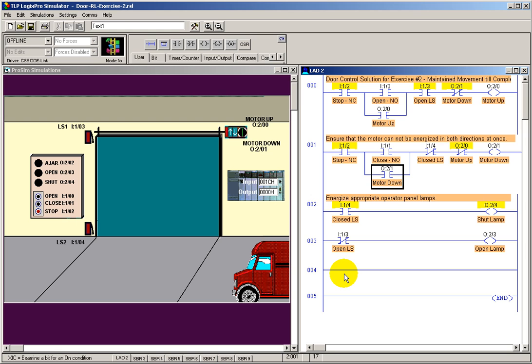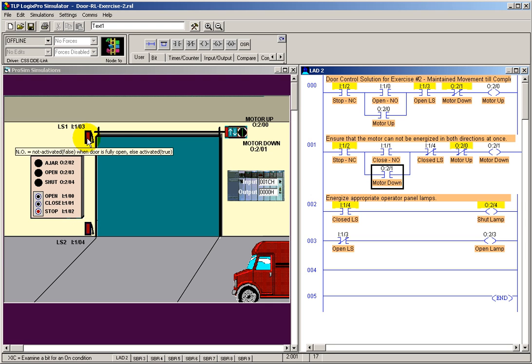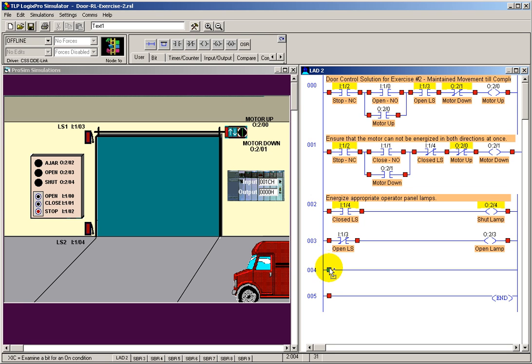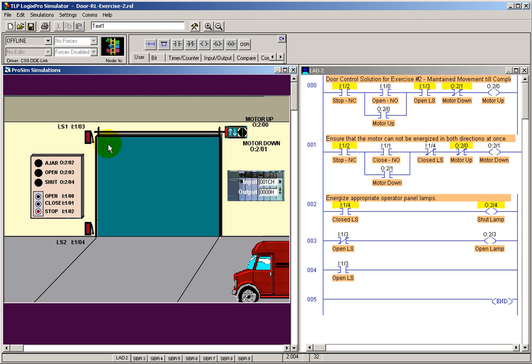Let's look at the ajar light. Let's think about what ajar is. Ajar means that it's somewhere above this limit switch and somewhere below this limit switch, the upper limit switch. When that condition, the ajar condition, is satisfied is when this guy is not activated and when this guy is activated. So let's put two instruction sets in our empty rung down here at the bottom. This one would be our input three. And it says, examine if closed. Well, this is closed any time it's not open, which means it's ajar. That's half the condition of being ajar, is that this guy is not fully open and it's activated, making this statement true.